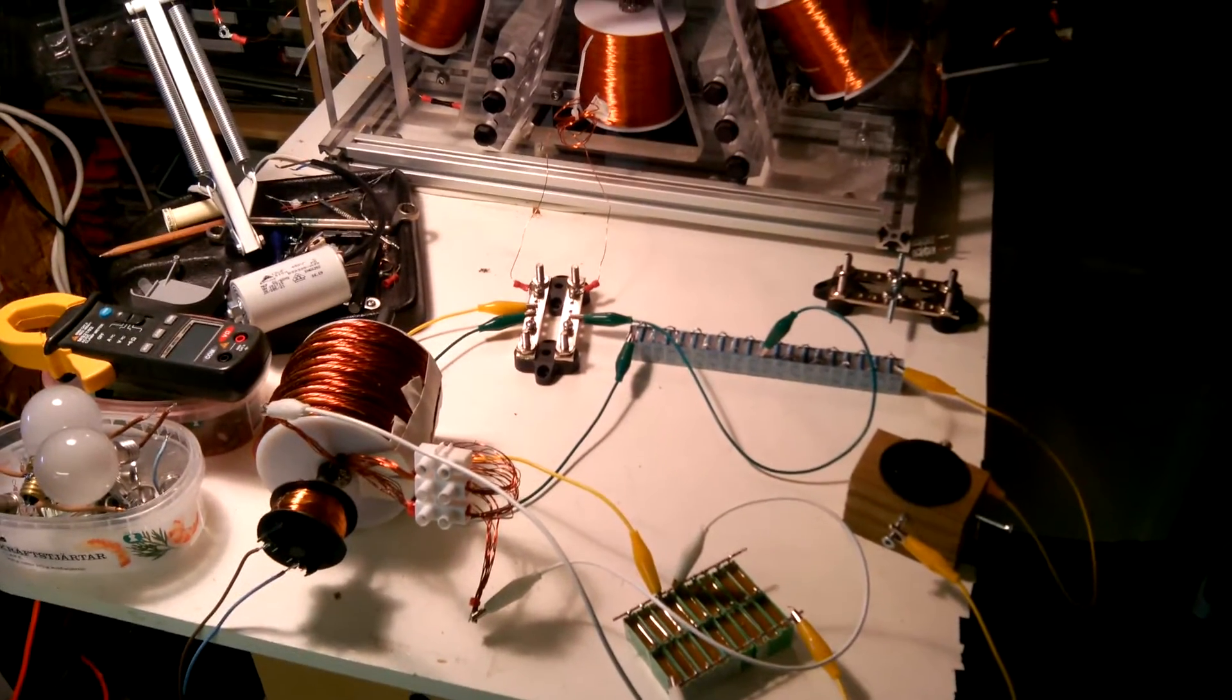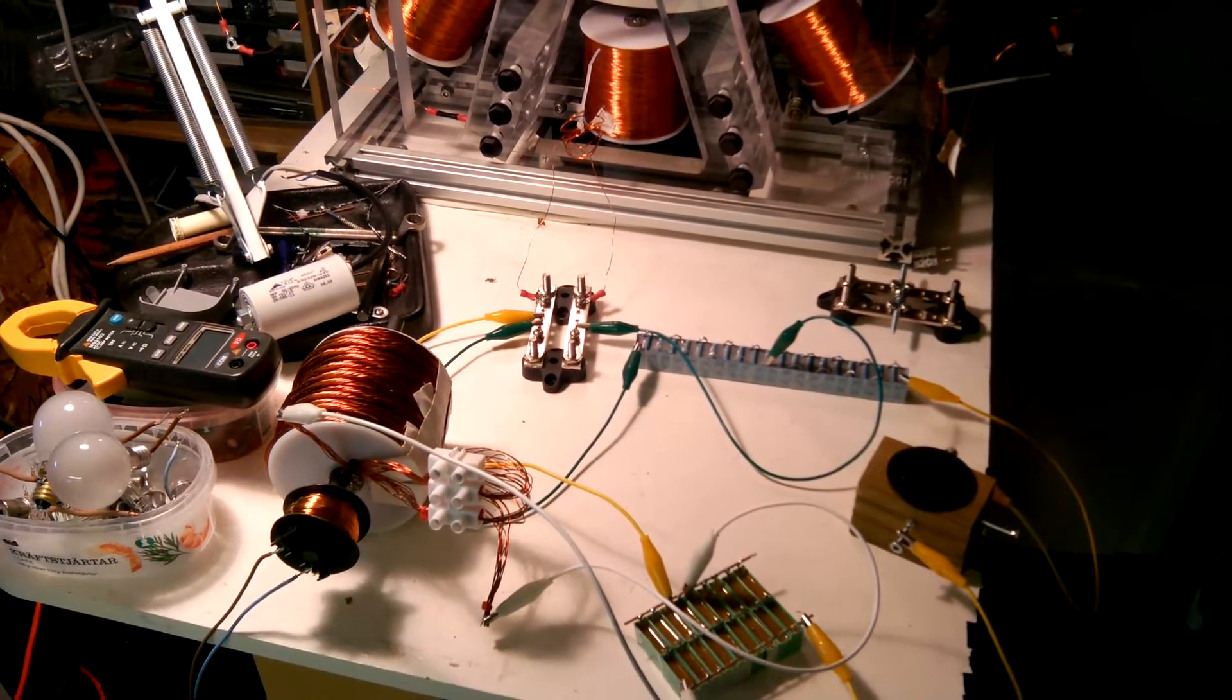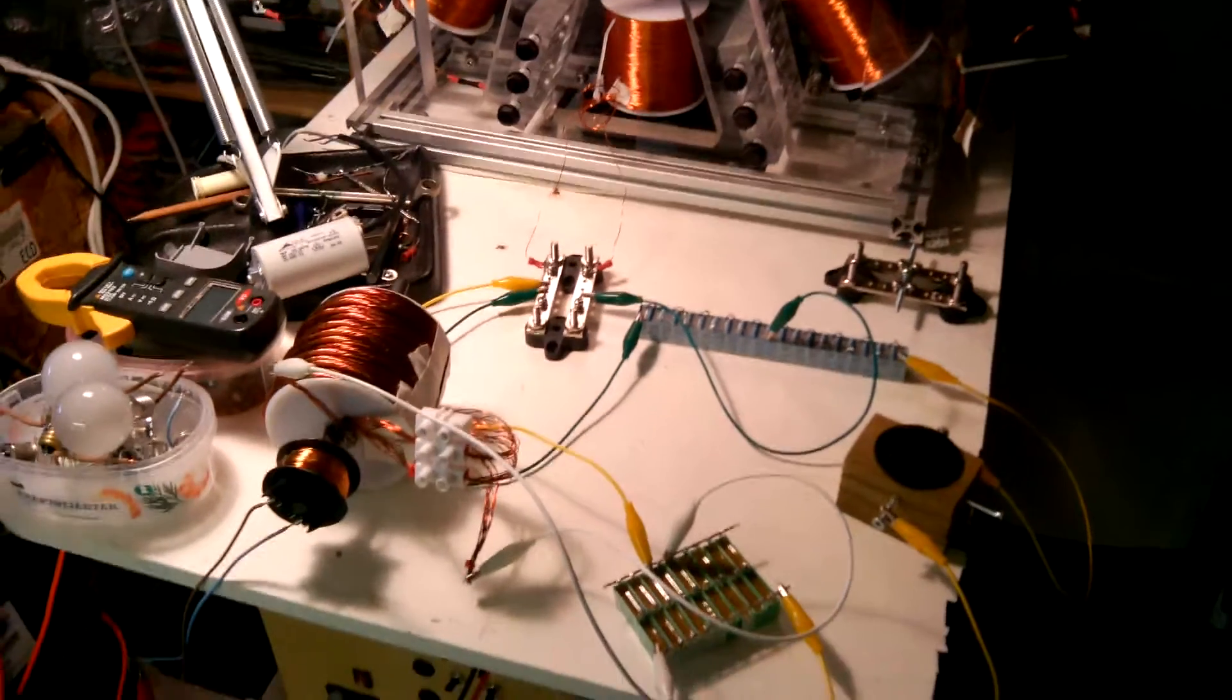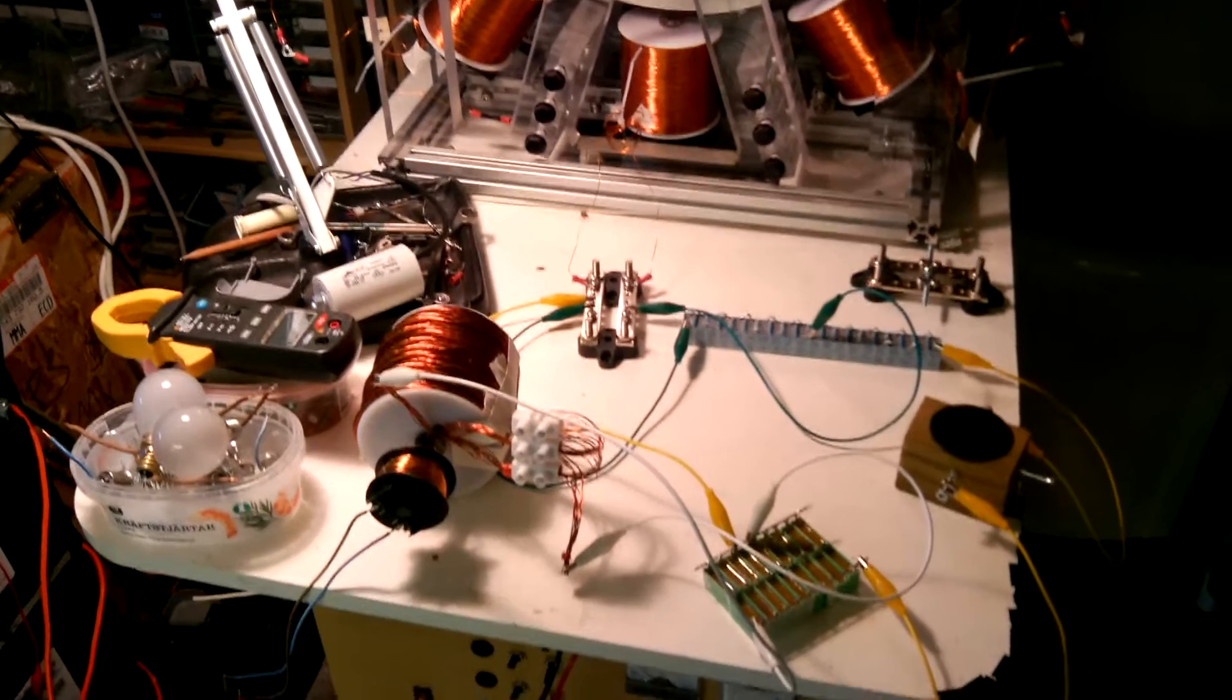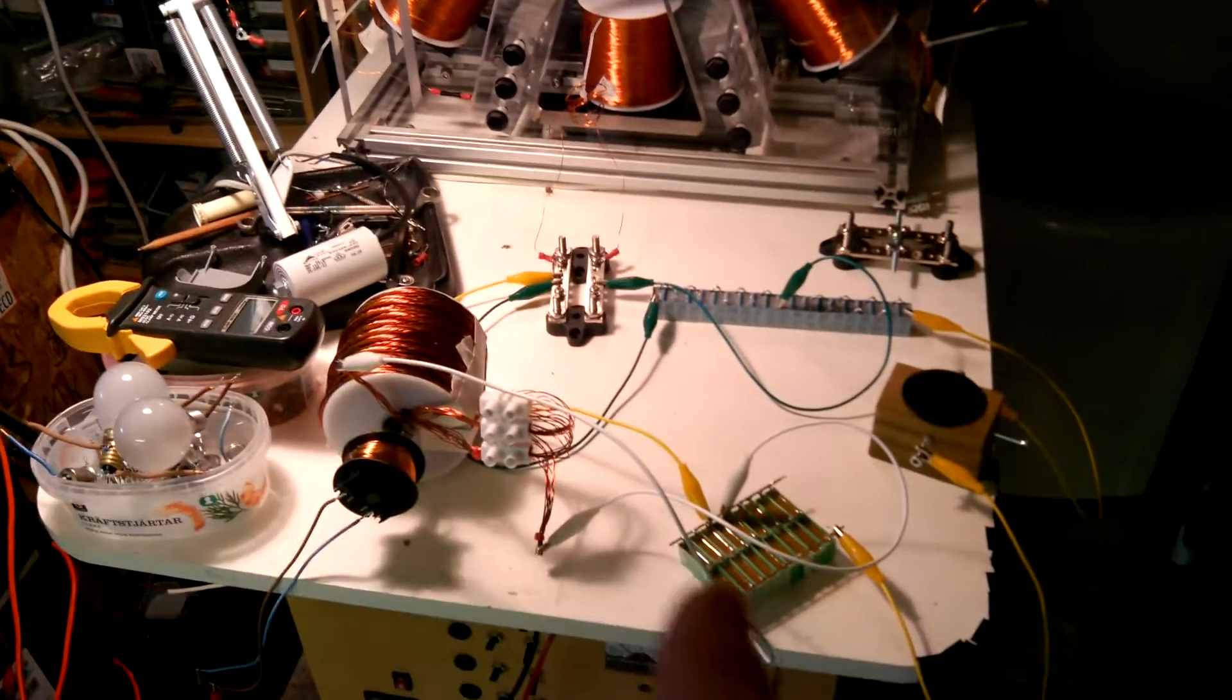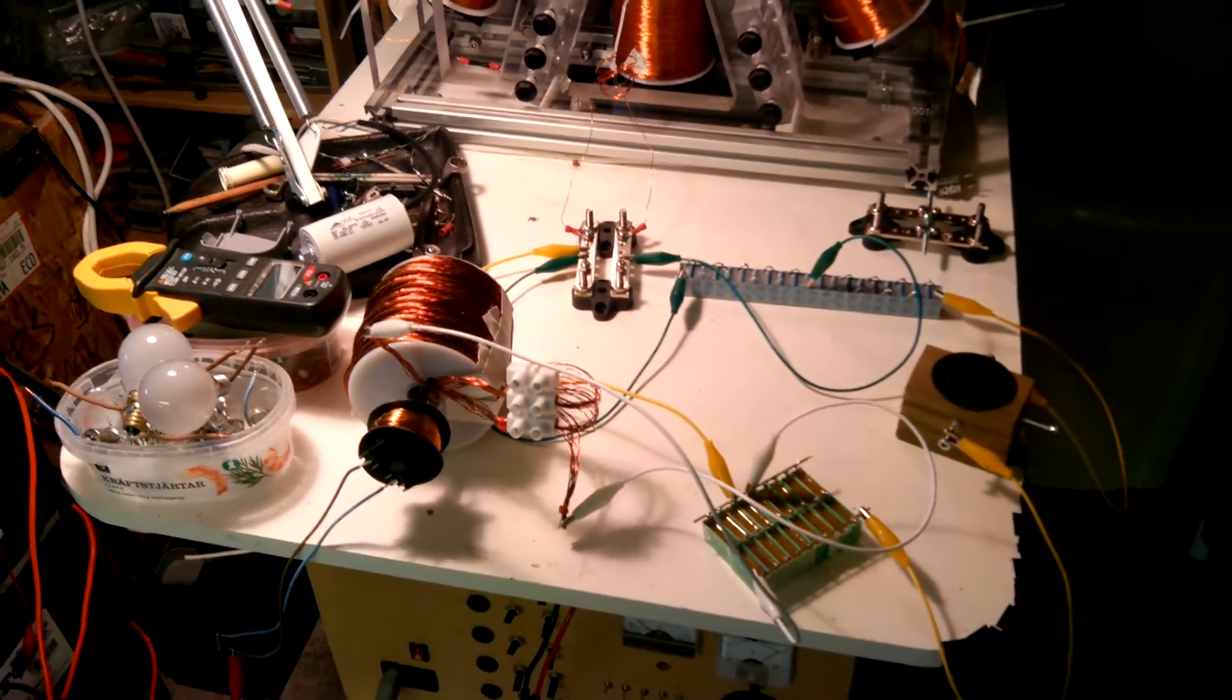So if the base frequency of the square wave is 150 Hertz, the next frequency within the square wave would be 450 Hertz. So this tank is tuned to 450 Hertz.